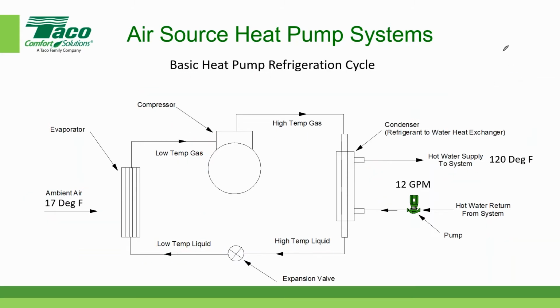Let's erase all of that stuff. So roughly what does the 17 degree Fahrenheit ambient air get cooled to? So what happens is that the ambient air at 17 degrees, when the temperature of the liquid down here is, let's say we said about 10 degrees, is usually about a 3-degree approach. So that means that it could go down to around 13 degrees. So it enters around 17, leaves about 13 degrees. Let's see, did I say, yeah, 10, about a 3-degree approach, 17 minus 3, 4 degrees, I'm sorry. So it would leave here at 4 degrees.